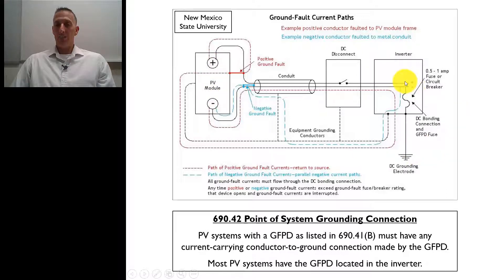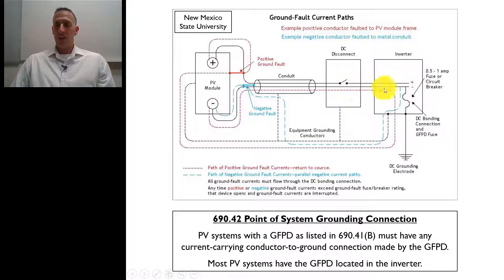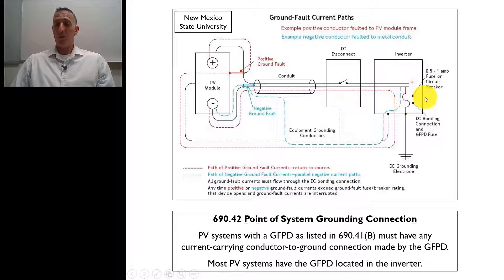When enough electrons flow through right here, when it flows through that fuse and it blows that fuse, the inverter shuts down, electrons stop flowing, and the system will disconnect — the system won't be operating anymore, and it'll let you know there's a ground fault.